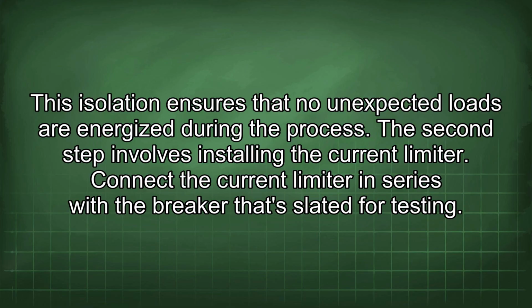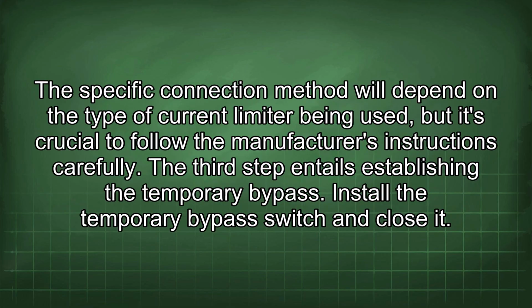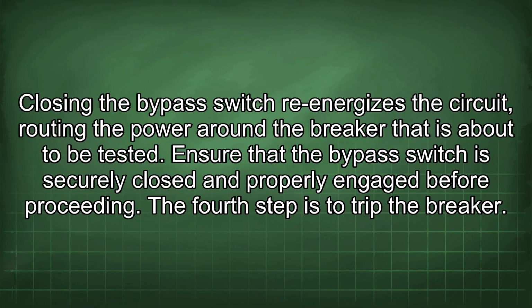The second step involves installing the current limiter. Connect the current limiter in series with the breaker that's slated for testing. The specific connection method will depend on the type of current limiter being used, but it's crucial to follow the manufacturer's instructions carefully. The third step entails establishing the temporary bypass. Install the temporary bypass switch and close it. Closing the bypass switch re-energizes the circuit, routing the power around the breaker that is about to be tested. Ensure that the bypass switch is securely closed and properly engaged before proceeding.